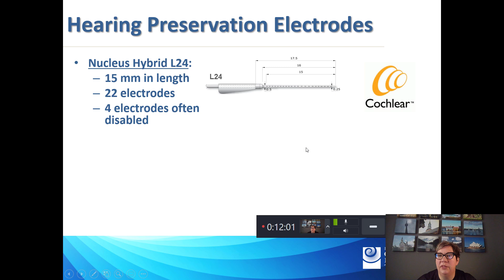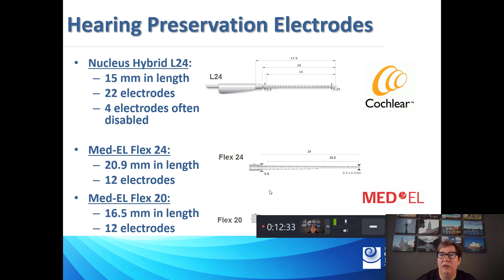MED-EL also has hearing preservation electrodes. They have the Flex 24, and if you look from electrode contact here to the tip, that's about 20 millimeters in length, so it's a little bit longer than our Flex 24, or than our hybrid L24. It has 12 electrode contacts. They also have a Flex 20, which is very comparable to the hybrid L24. It's 16 millimeters in length and has 12 electrode contacts.